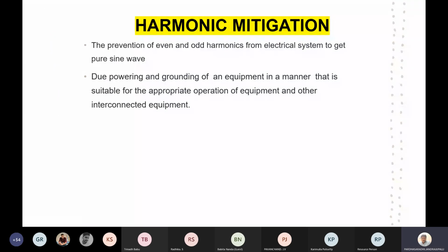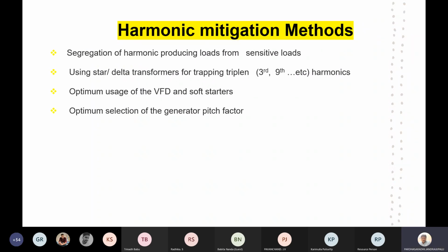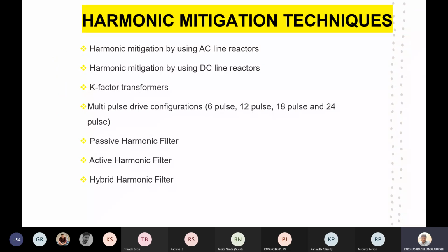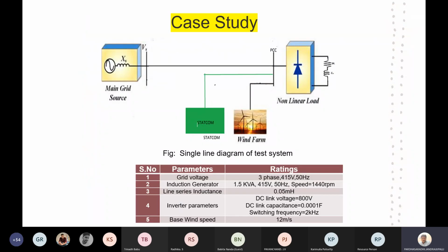These non-parametric approaches have good advantages. Finally, we will talk about the mitigation techniques: the prevention of even and odd harmonics in the electrical system to get a pure sinusoidal wave. This includes proper powering and grounding of equipment in a manner suitable for the appropriate operation of the equipment and other interconnected equipment. Coming to the harmonic mitigation methods: segregation of harmonic-producing loads from sensitive loads, use of star-delta transformers, optimal usage of variable frequency drives and soft starters, and optimum selection of generator pitch factor. There is also a provision for mitigating harmonics by AC line reactors, DC line reactors, K-factor transformers, multi-pulse drive configurations like 6 pulse, 12 pulse, 18 pulse and 24 pulse, passive harmonic filters, active filters, and hybrid harmonic filters.